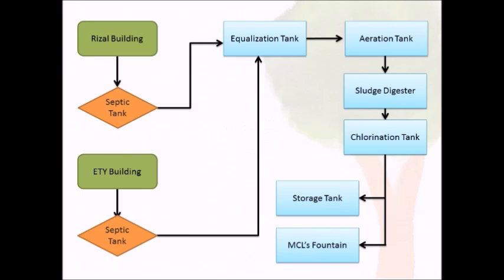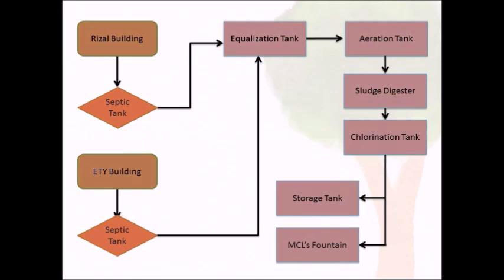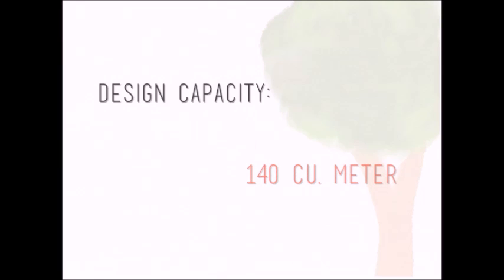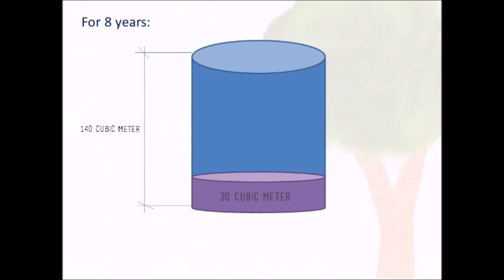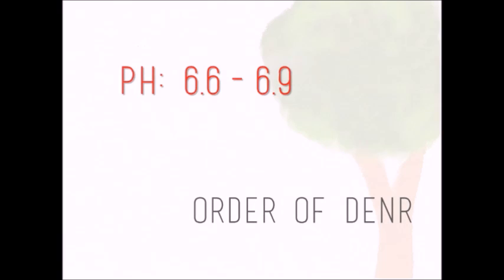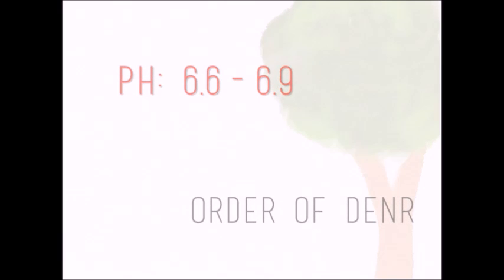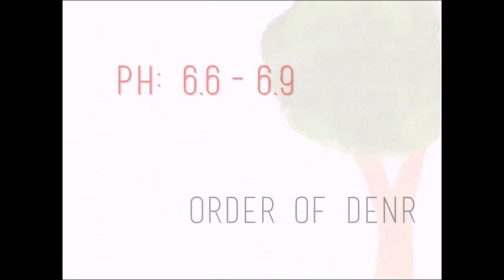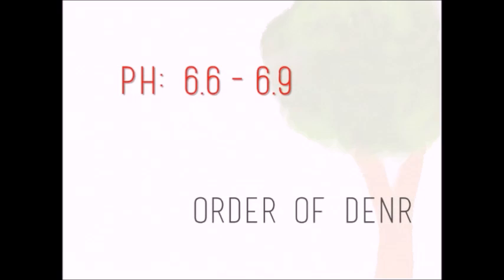Let's take a look first on the treatment processes in the MCL wastewater. The design capacity of the MCL's wastewater treatment facility is to hold 140 cubic meters of settled waste, what we called sludge. As of now, only 30 cubic meters of sludge is in the digestion tank for the 8 years since it started to operate. The pH remained to be in between 6.6 to 6.9, as per order set by the Department of Natural Resources.